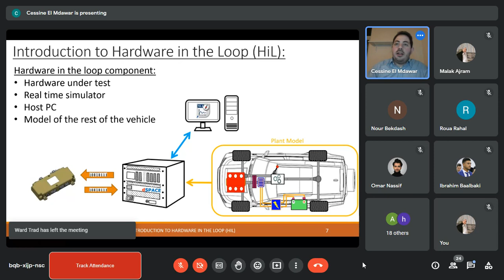One of the challenges when realizing hardware in the loop is there are three main challenges. One of them is inter-step switching. Like I mentioned, the heavier the model, the more accurate but the slower it is. That means if we're running a very accurate model, I might have a very large time step. So assuming I want the model to give me data every 1 millisecond, a model running at a 1 millisecond time step needs to be less accurate than one giving data every 100 milliseconds.